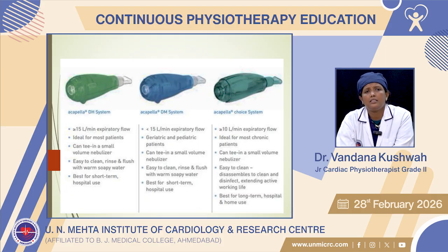First, green, for expiratory flow of more than 15 liters per minute, ideal for most patients. It can be used with a small volume nebulizer, is easy to clean, rinsed and flushed with warm soapy water, and is best for short term hospital use.